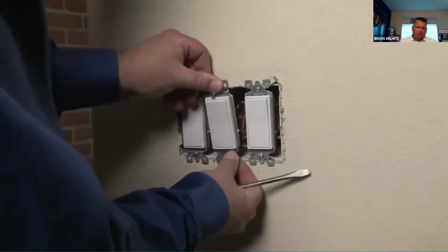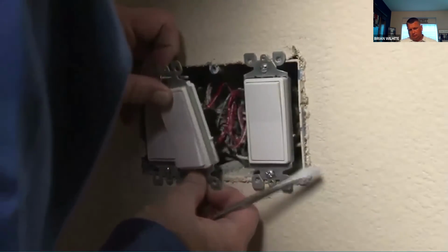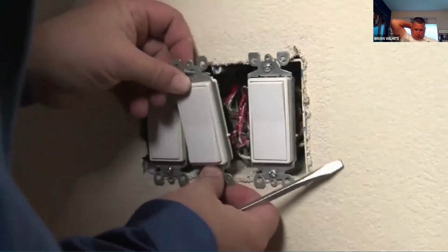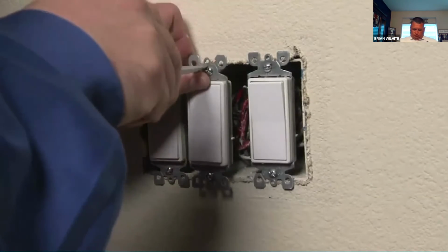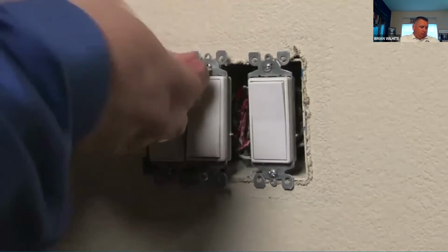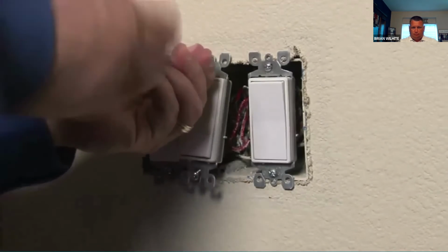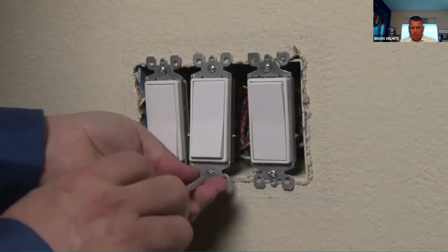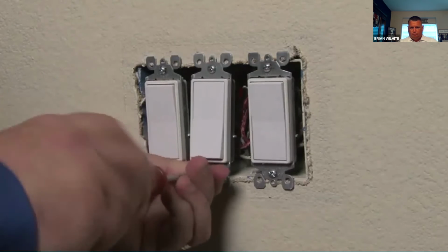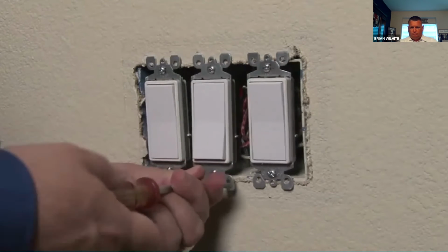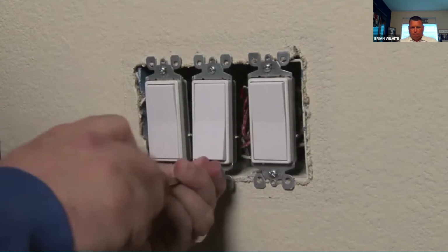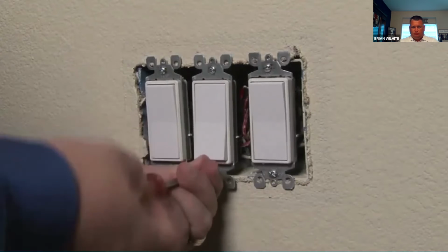Okay, technician is now going ahead and putting the switch back into the wall. Making sure that the wires are going in there straight and not binding in any way. He tightens up one screw. Keep in mind not to over tighten. And then the bottom screw to the switch. Our technician has now replaced the switch, and we've removed the lockout tagout, and that's how you replace a bad switch.